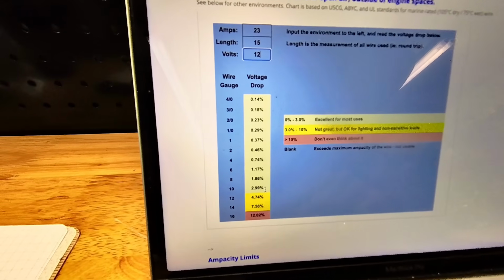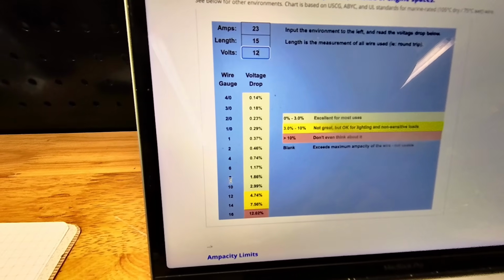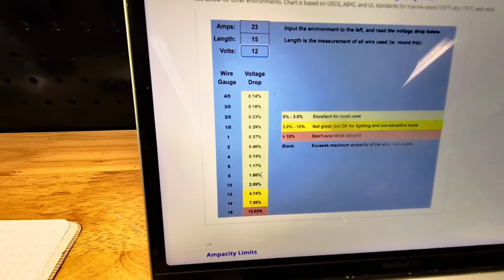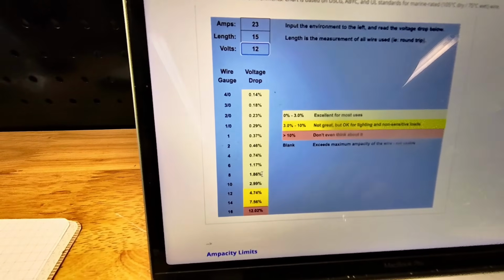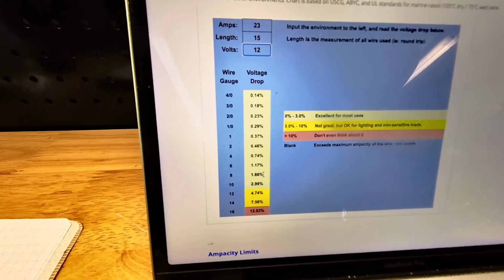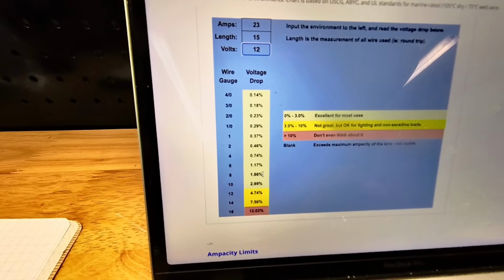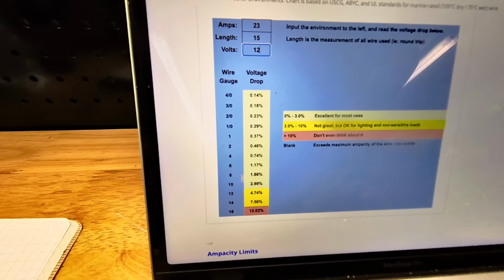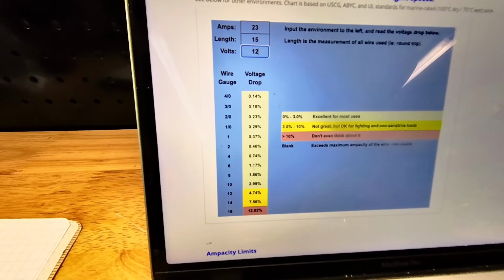Like I said, I'm not crazy about 3%, so I'd like to do one better. I'm going to go with 8 gauge wire here, which gives a 1.8 to 1.9% voltage drop. That's very tolerable for the loads we're going to run, so we're going with 8 gauge wire for this system.